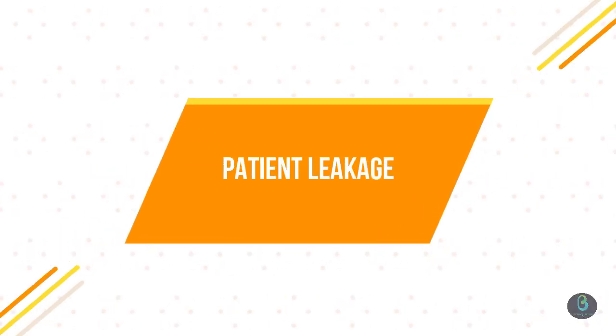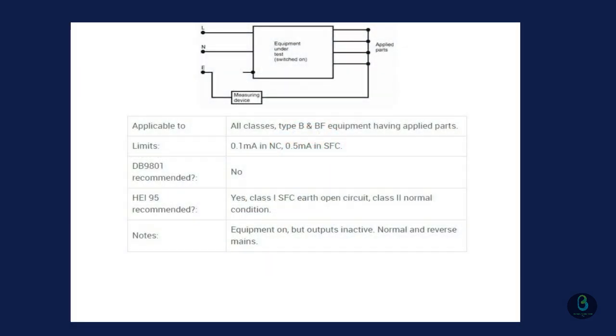Patient Leakage. By applying mains voltage to the applied parts, the leakage current that would flow from an external source into the patient circuits can be measured. Although the safety tester normally places a current limiting resistor in series with a measuring device for the performance of this test, a shock hazard still exists. Therefore, great care should be taken if the test is carried out in order to avoid the hazard presented by applying mains voltage to the applied parts.